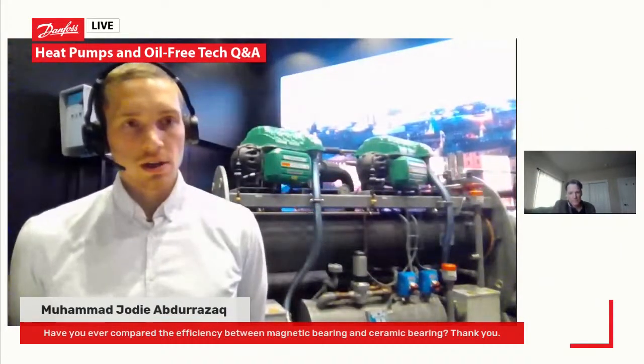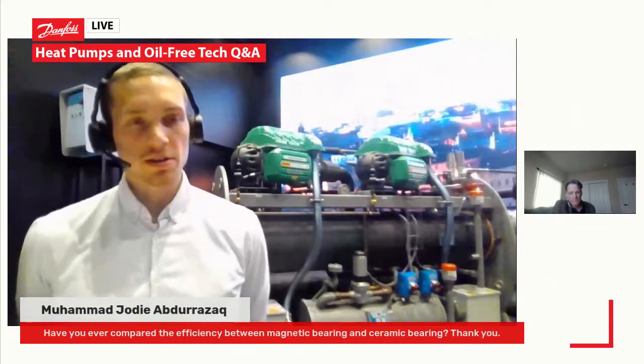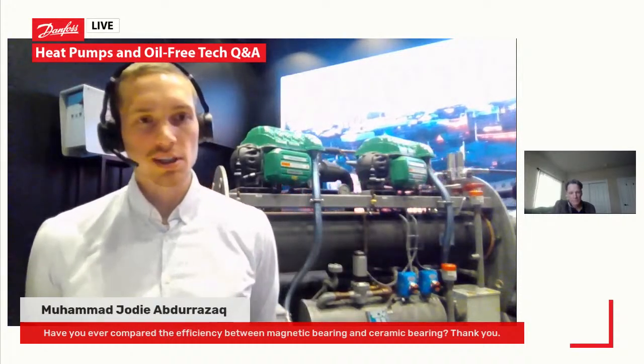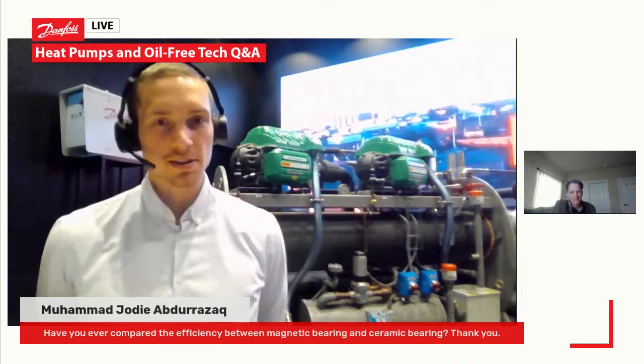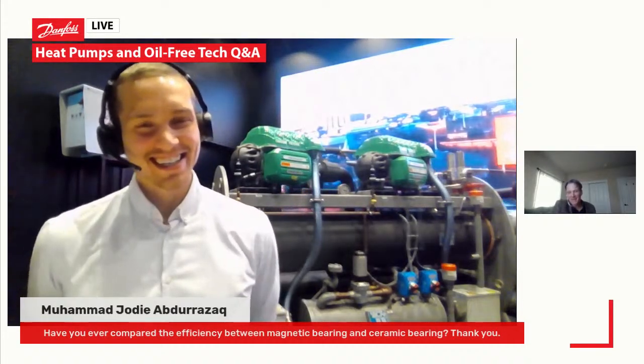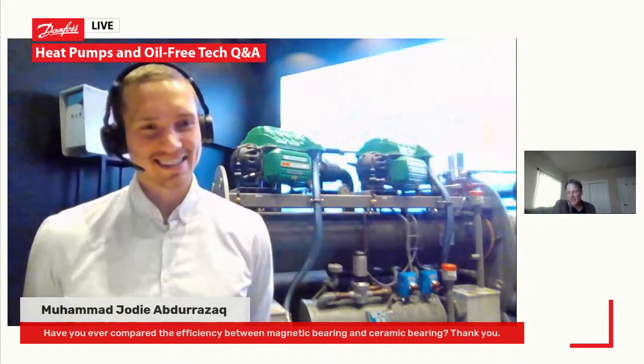I believe that was also one of the reasons the original inventor of Turbocor didn't go with the ceramic bearing system. That was part of his evaluation at the time. He had the choice of magnetic, ceramic, and now what's evolving is gas, which will come about in the future as this technology pushes into smaller capacities. But at the time, the choice was really to go oil-free, either ceramic or magnetic. If you start with a steel ball and steel race, it's much easier to go ceramic. But he was starting with a clean sheet, and he determined at the time, and we still believe now, that the magnetic bearing is the best choice.